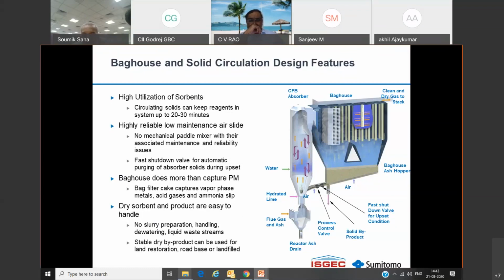Then the bag house can capture a very high dust burden. And here we do not have a limitation of inlet dust like wet FGD. If we increase the inlet dust to wet FGD going above a certain value, it will start creating problems in operation, maybe for several reasons. There could be erosion because of high ash. However, in this technology we can accept a much higher ash dust burden, and that dust can be collected in the bag filter, and at the outlet we can achieve much lesser dust emission.